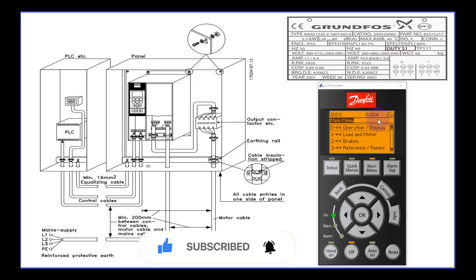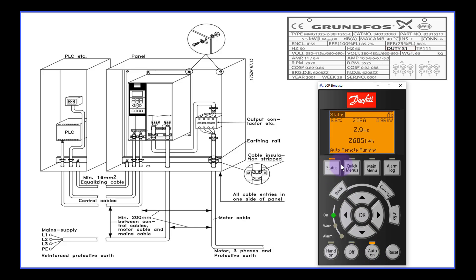To do the initialization, let's say the VFD is still on. You can see from the LED light or the auto-on indicator. What you need to do is press the off button to turn off the VFD. Make sure the VFD is off before you do any parameter setup.